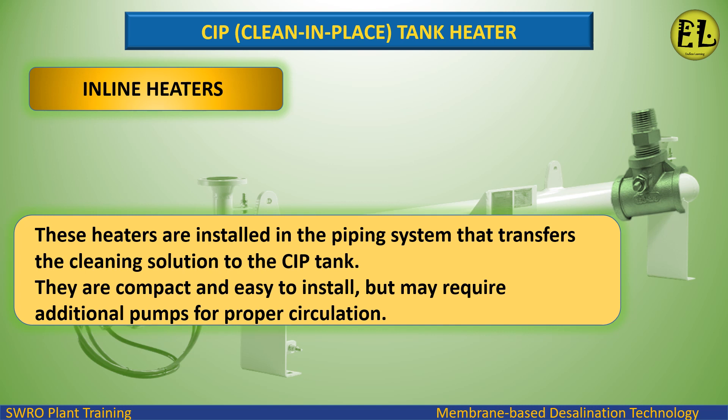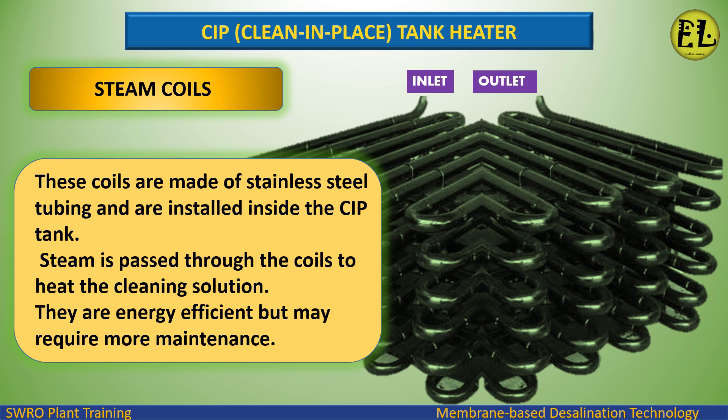Inline heaters are installed in the piping system that transfers the cleaning solution to the CIP tank. They are compact and easy to install but may require additional pumps for proper circulation. Steam coils are made of stainless steel tubing installed inside the CIP tank; steam is passed through the coils to heat the cleaning solution. They are energy efficient but may require more maintenance.